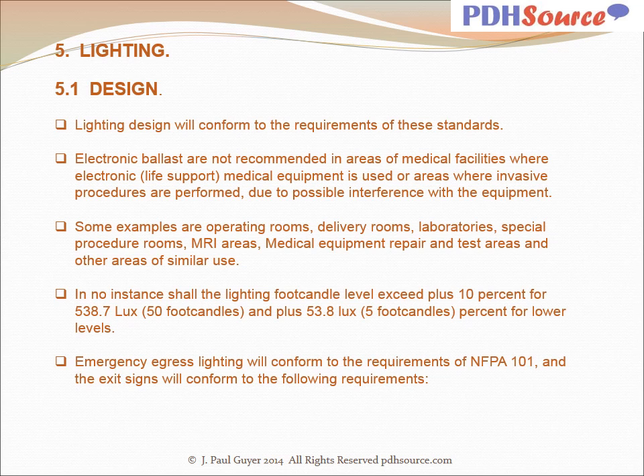Electronic ballasts are not recommended in areas of medical facilities where electronic life support medical equipment is used or areas where invasive procedures are performed due to possible interference with the equipment. Some examples are operating rooms, delivery rooms, laboratories, special procedure rooms, MRI areas, medical equipment repair and test areas, and other areas of similar use. In no instance shall the lighting foot candle level exceed +10% for 50-foot candles and +5 foot candles for lower levels. Emergency egress lighting will conform to the requirements of NFPA 101, and the exit signs will conform to the following requirements.